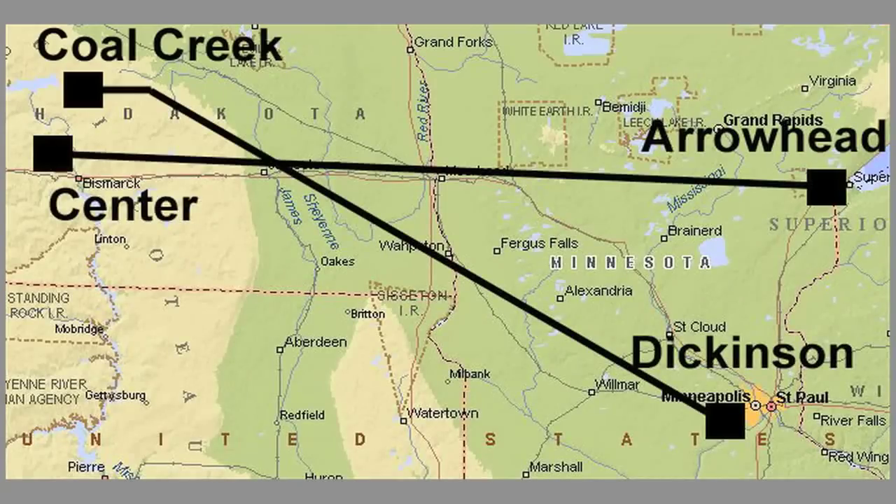Over this time, the GE projects tended to be the smaller ones, but all of them were successful — completed, met the commitments. I believe ASEA did reasonably well over time once they got around their water cooling problems. They also had insulation failures in the CU project; I think they misapplied the surge arresters. They were very resourceful — we were designing our systems with one panel of thyristors as spare, while they designed theirs with a whole pole, a whole half of the system, in the warehouse.